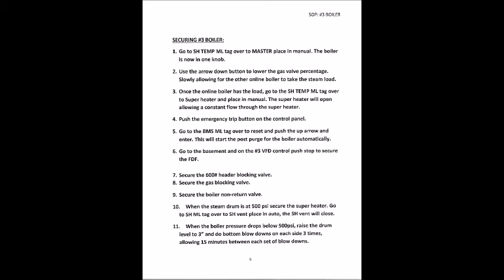10. When the steam drum is at 500 psi, secure the superheater. Go to SH ML, tab over to the SH vent, place in auto, and the SH vent will close. 11. When the boiler pressure drops below 500 psi, raise the drum level to 3 inches and do bottom blowdowns on each side 3 times, allowing 15 minutes between each set of blowdowns. 12. Secure the feed water station. 13. Notify chemistry to secure the unilock system.